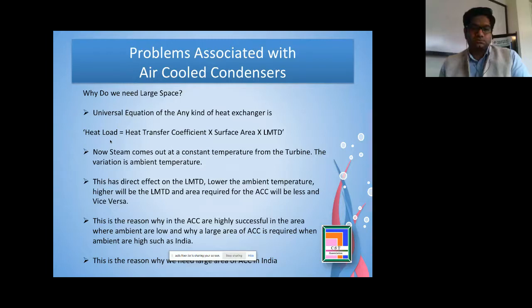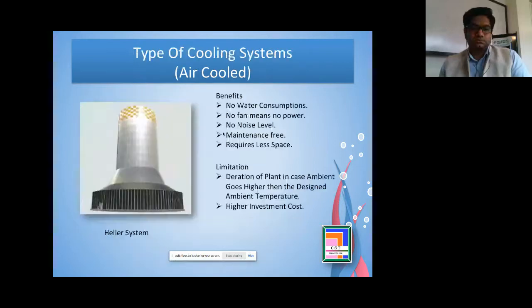But at that time we are losing a great amount of power also, because every minute, every second, every hour the power is generated and the billing is being done. So at that point we lose a lot of power and money also. That's why ACC in India, it is very difficult for ACC to work, because of the high ambient temperature. So the option left is basically using adiabatic coolers, and then another type of air-cooled condenser is the Heller system.